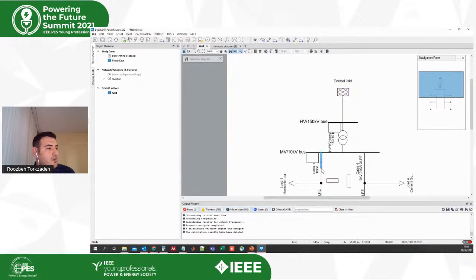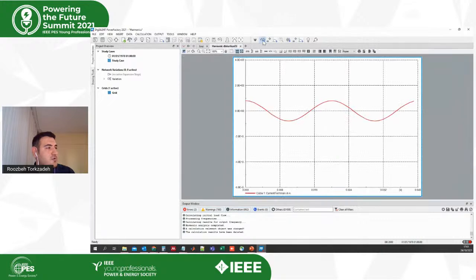Now let's see what the waveform of this line looks like. I'll run the harmonic load flow again, and you can see the distortion in the current once more. This distortion isn't because you're producing the harmonic, but because someone else elsewhere in the grid is producing it, and it can impact you.